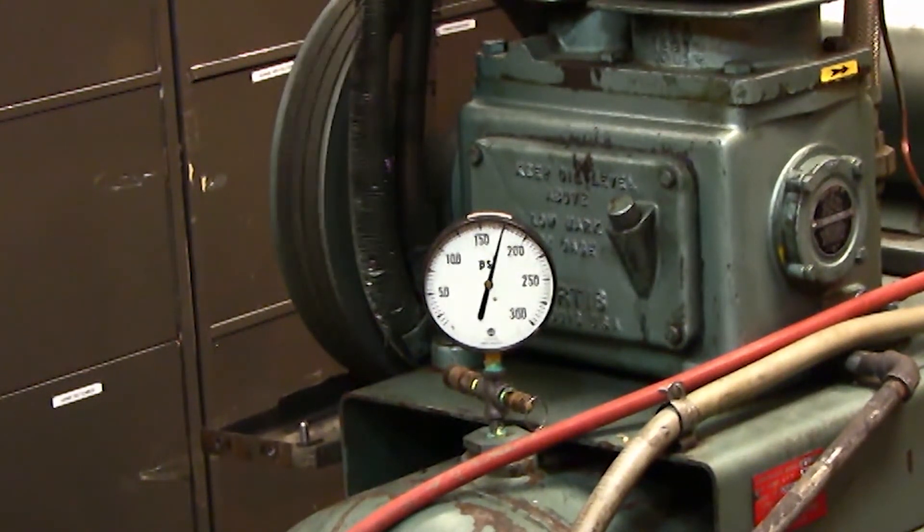But look at it to start this air compressor. It starts it right up. We're running right against the pressure in the tank because I have the unloaders disconnected.